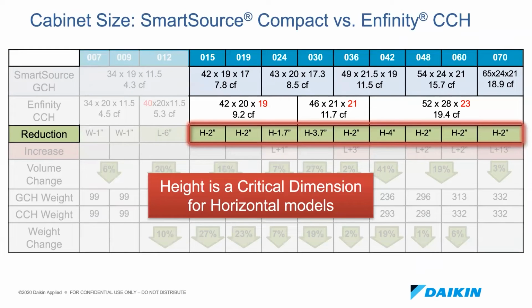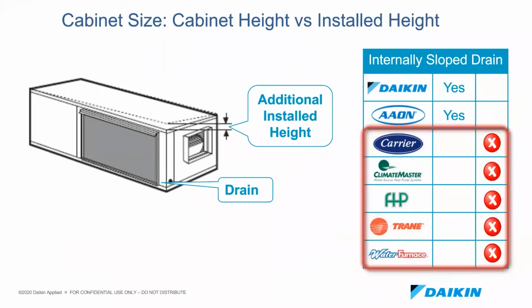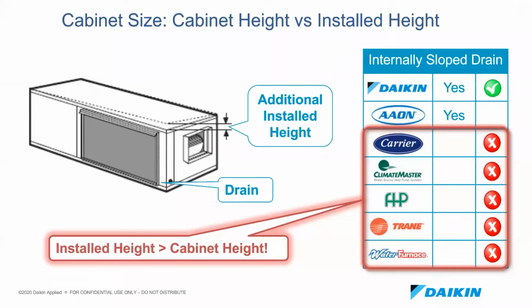The height is often a critical dimension for horizontal units since they are hung above the ceiling. The Smart Source Compact will be up to 4 inches shorter than the same size Enfinity model. Daikin's drain pan is internally sloped, therefore the unit can be installed level and the condensate will drain naturally from the pan. This means that our cabinet height is the installed height of the unit. For the competitors' units that have a drain pan that's not internally sloped, their unit must be installed with a pitch to ensure the condensate drainage. So their installed height will be greater than their listed cabinet height.